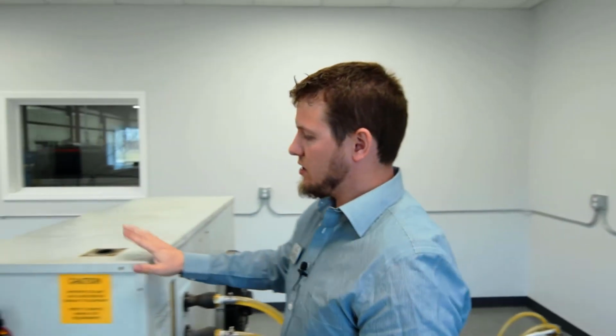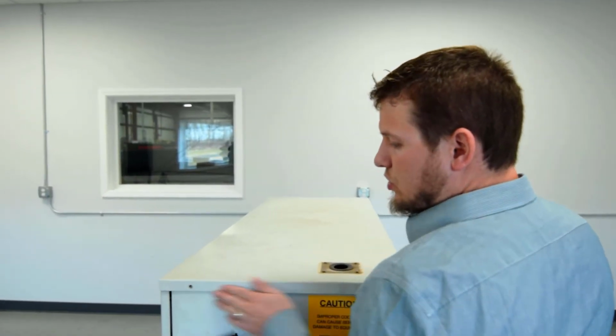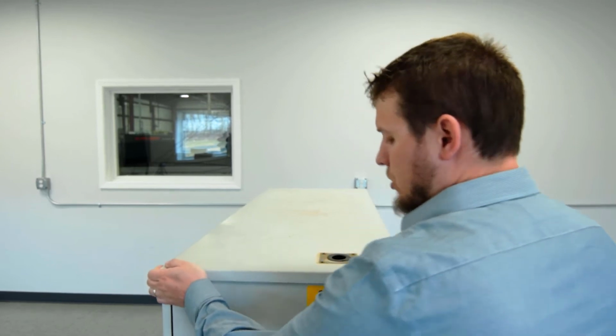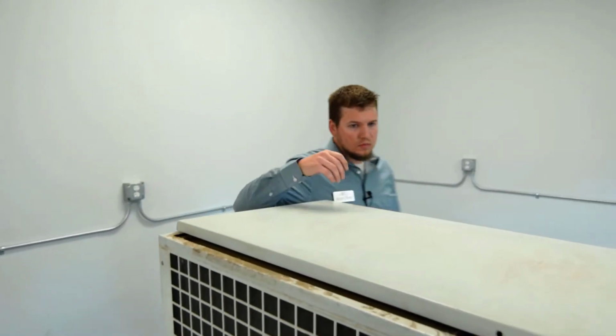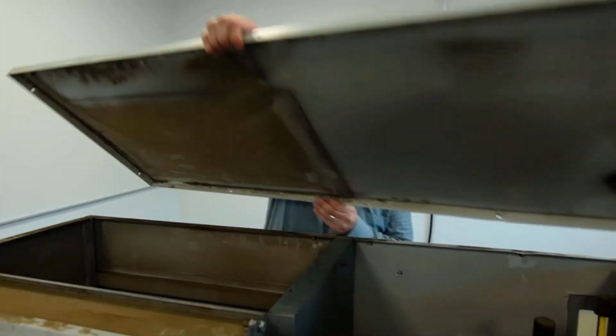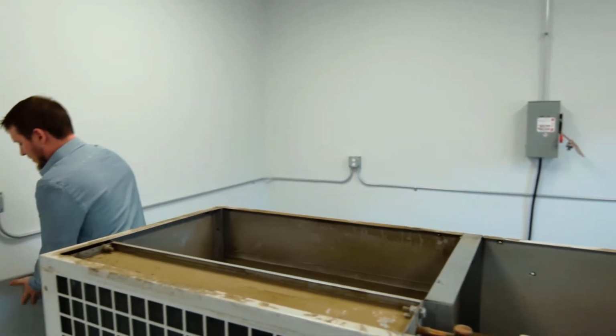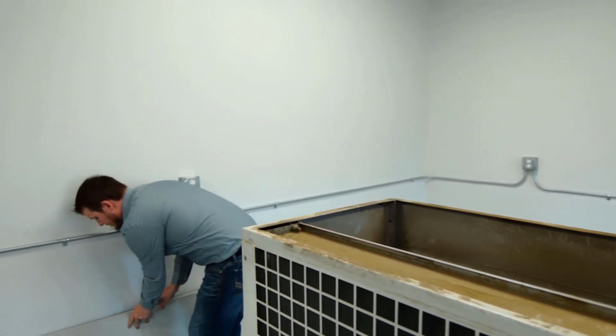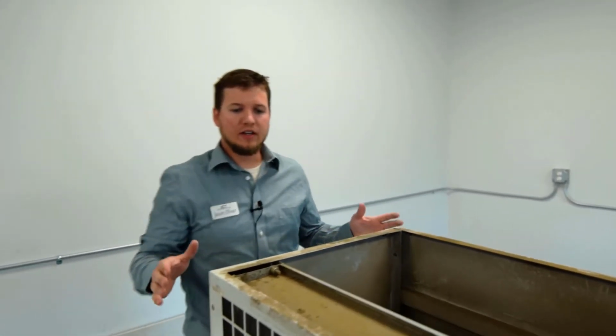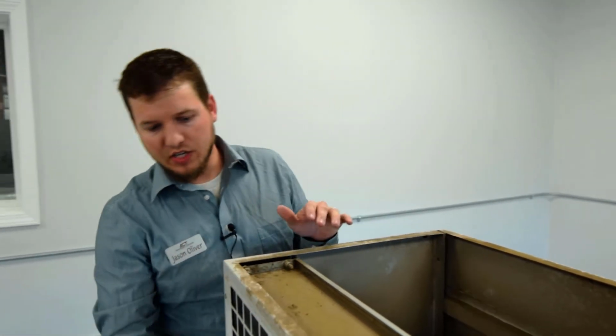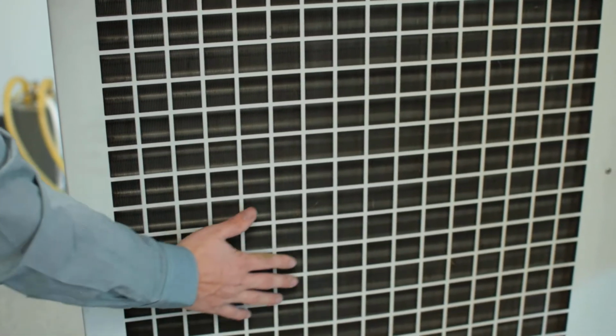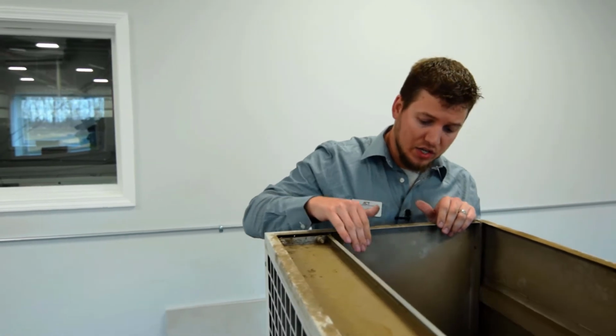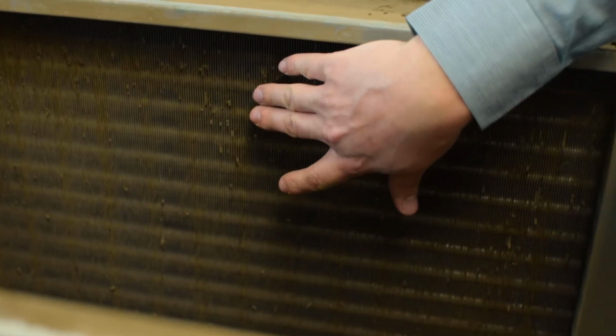The next step on this is going to be to remove the top cover. Once you removed all the screws, you can just lift this cover up and go ahead and remove and just set off to the side for now. From here, we're going to have access to the condenser coil. As you can see from the outside, it looks pretty clean, but if you look on the inside here, you can tell that this coil hasn't been cleaned from the inside in a very long time.